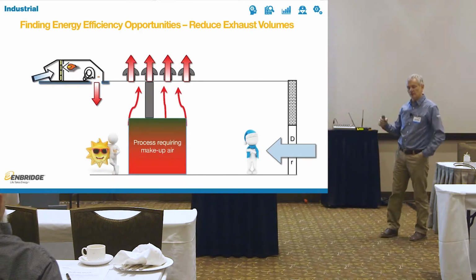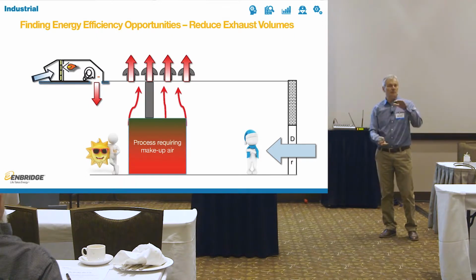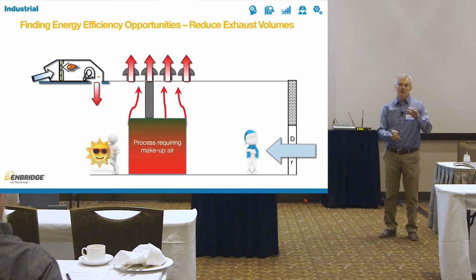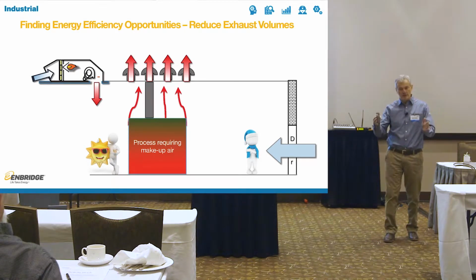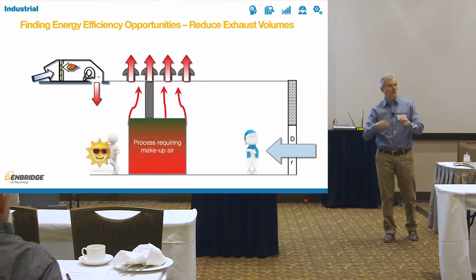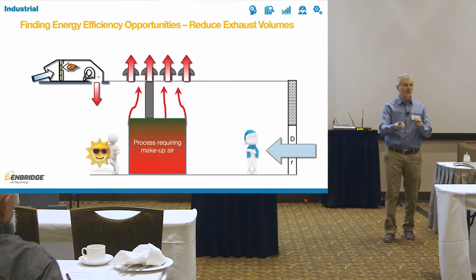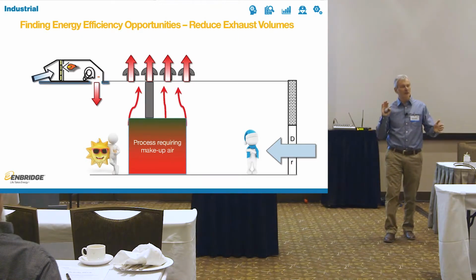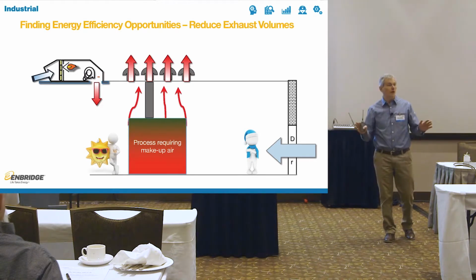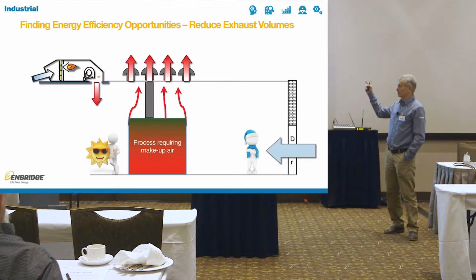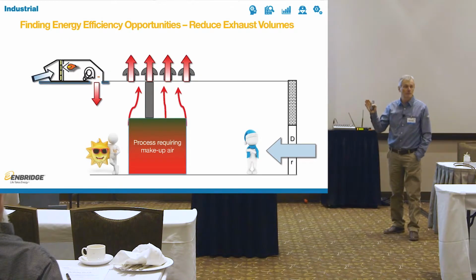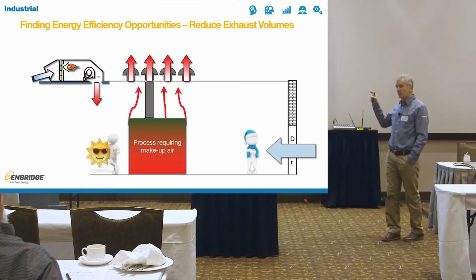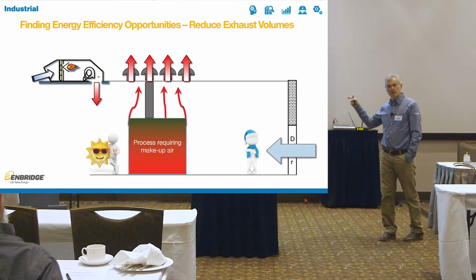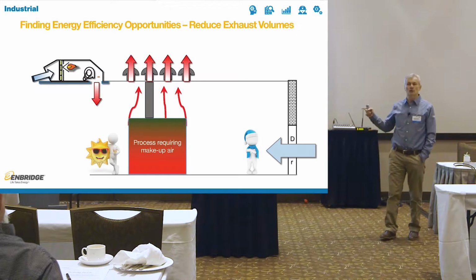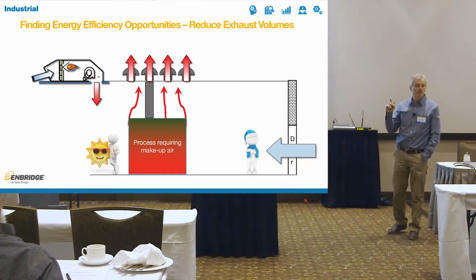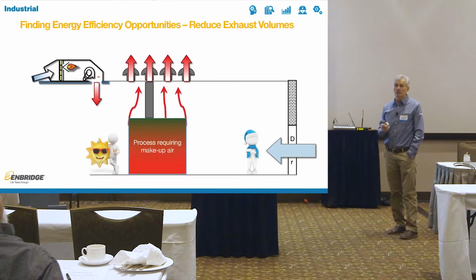I worked in a facility where we made coils for cars, springs. We made 16 million of them a year. You do it by heating the steel rod to red hot, winding it, and then annealing it. We had 12 furnaces inside, high heat ovens, annealing ovens. It was hot. So if somebody didn't want to put in exhaust in the summertime, they would be crazy. There is no way you can work without it. The problem is that those exhausts are put in one at a time, and we never have time, and we never have money to actually interlock them to anything. They're just there. Because in August, you don't need to interlock them. The more they run, the better.